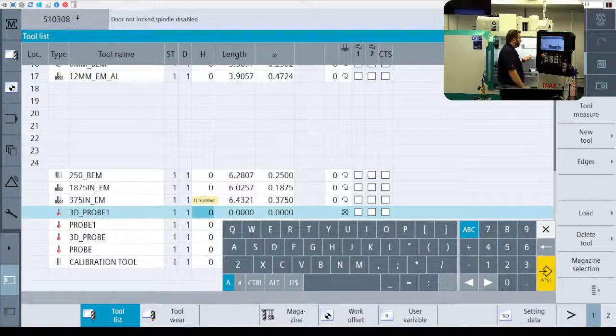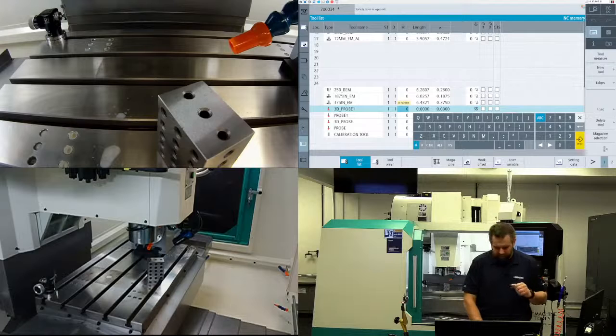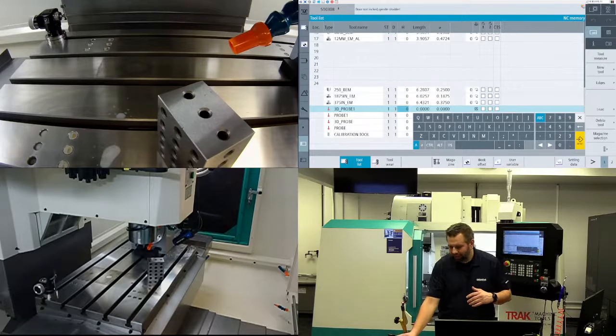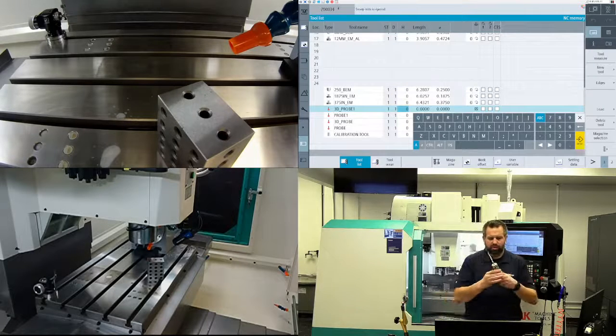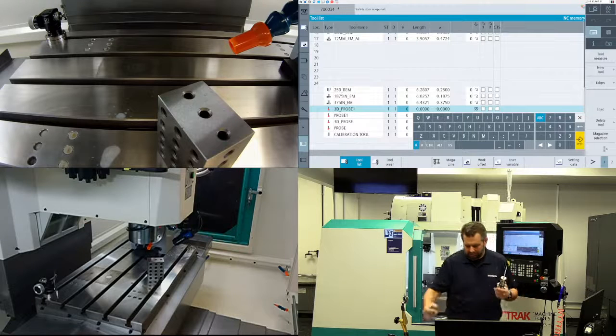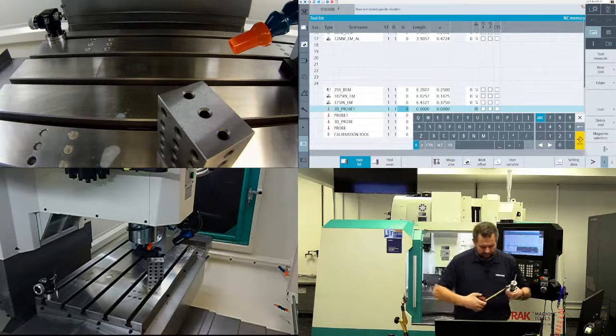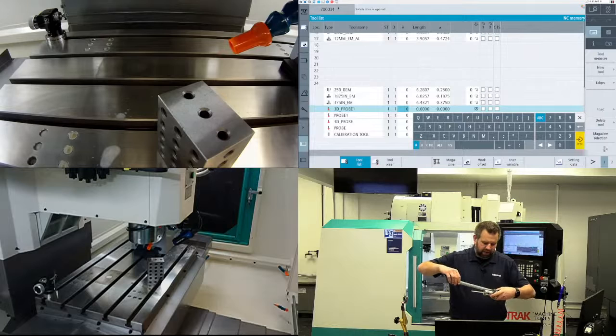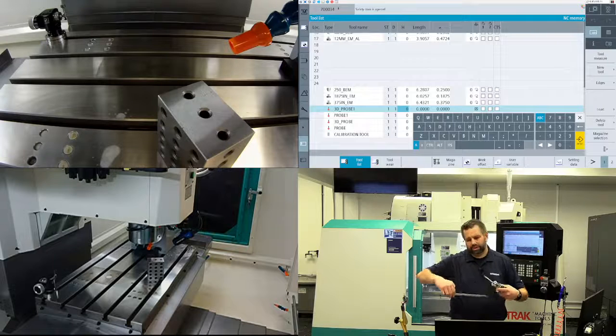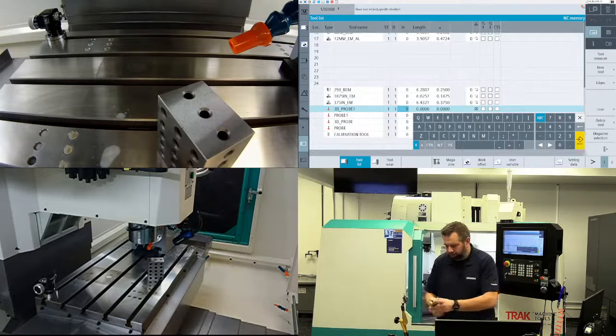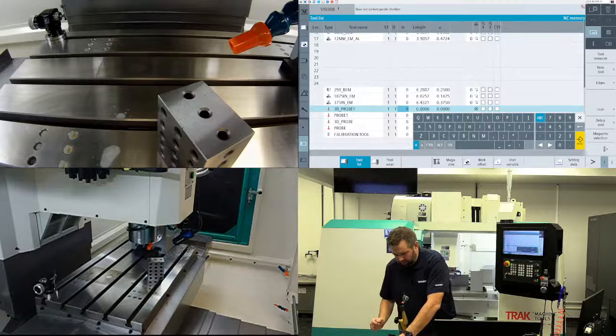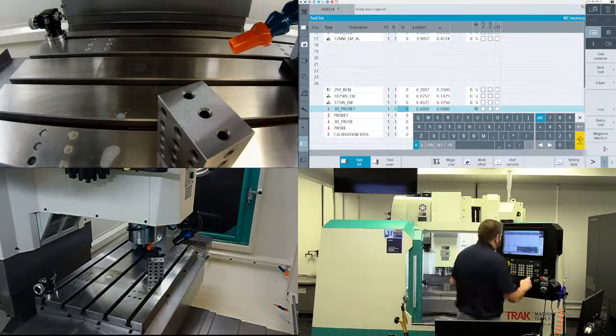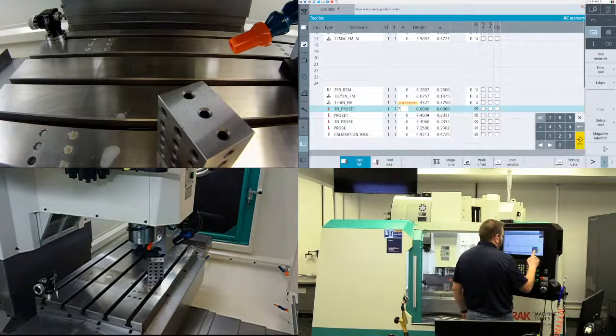And then once we get it in there, we got to add some things. So a couple things that we need to do is we need to give it some known length, right? We got to give it some known length. So I got a tape measure here. And roughly all I'm going to do is just kind of get the gauge line to the tip of the stylus. I'm running at like 7 1/4 on this probe, and that's all I'm going to put in there. So I'm going to go back to the control, and I'm going to put in 7 1/4.